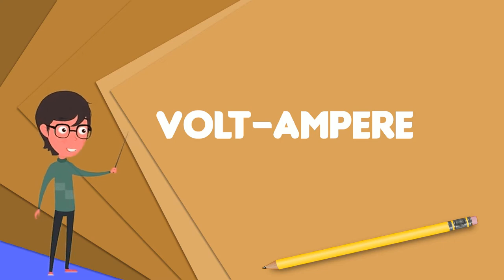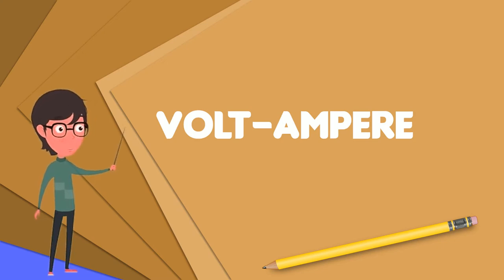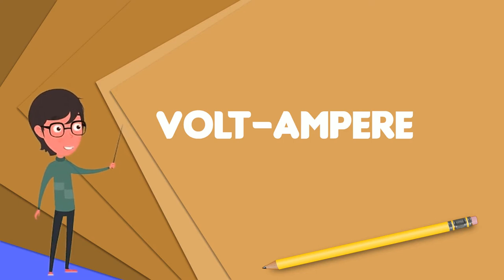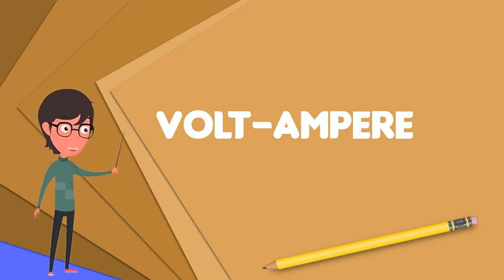Some devices, including uninterruptible power supplies, have ratings both for maximum volt-amperes and maximum watts. The VA rating is limited by the maximum permissible current, and the watt rating by the power handling capacity of the device.